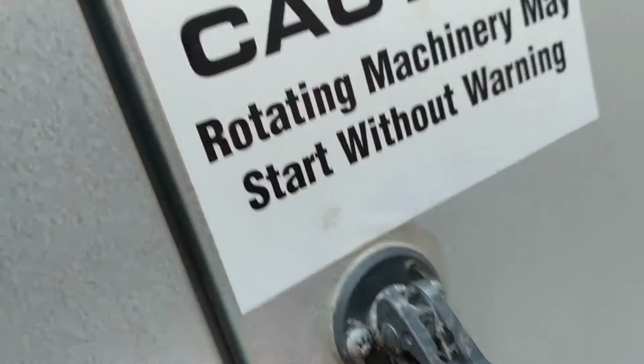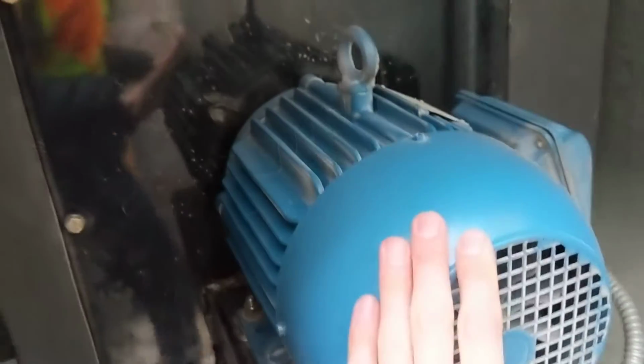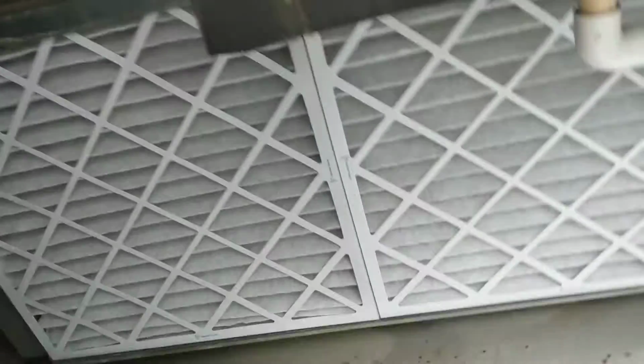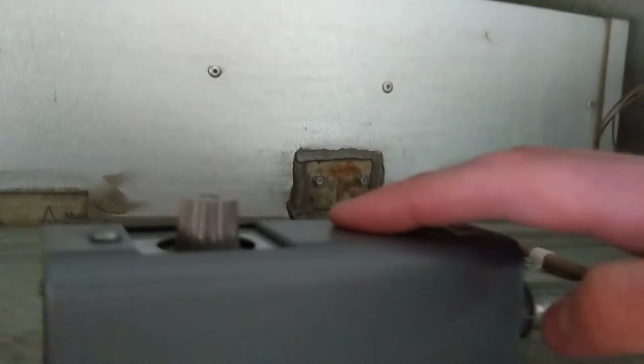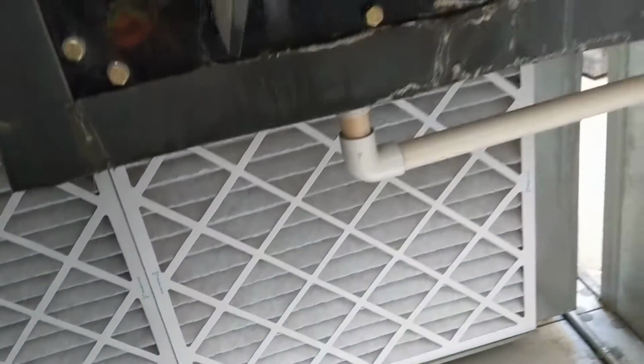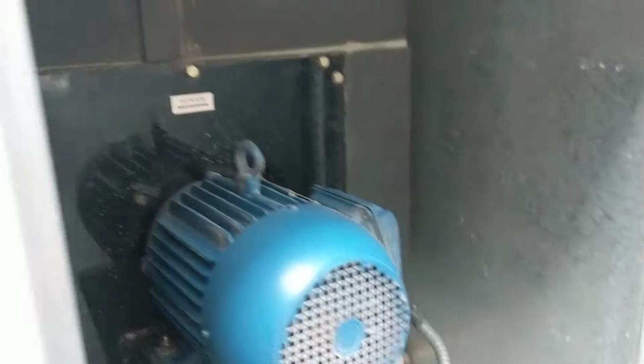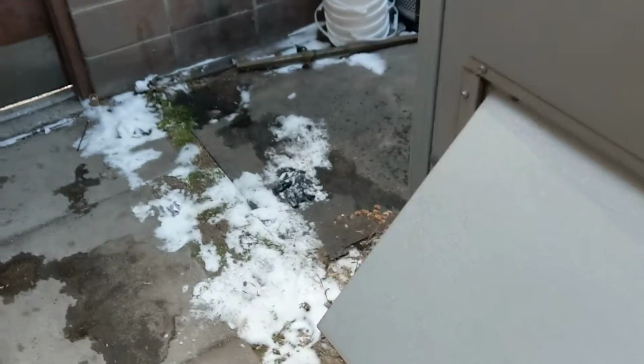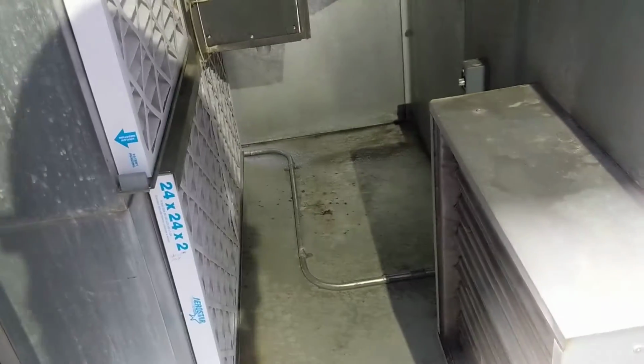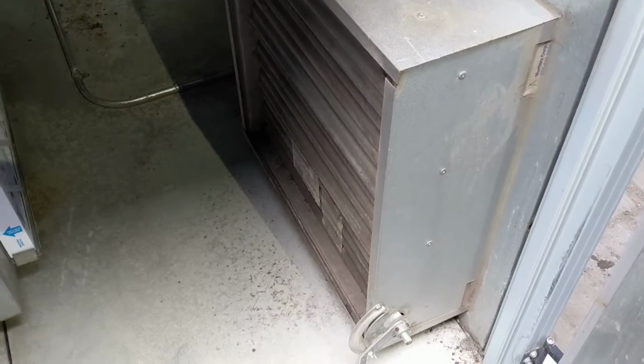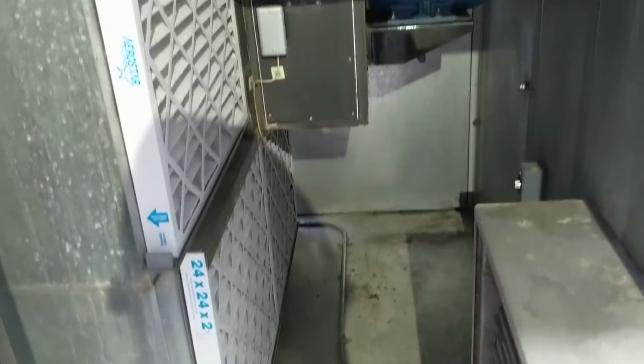And so over here, this motor here does your burner airflow. These are your filters for your air. This here, this is what controls the temperature setting for the air. So the point of that is, if the outside air is too cold, it would be coming in through there, it'll shut the unit on and off based on the outside air temperature, because actually if it's cold enough outside, then you theoretically wouldn't need the unit to run. In our case, this is actually closed off, and I think that's going to get changed with the BMS system being added.